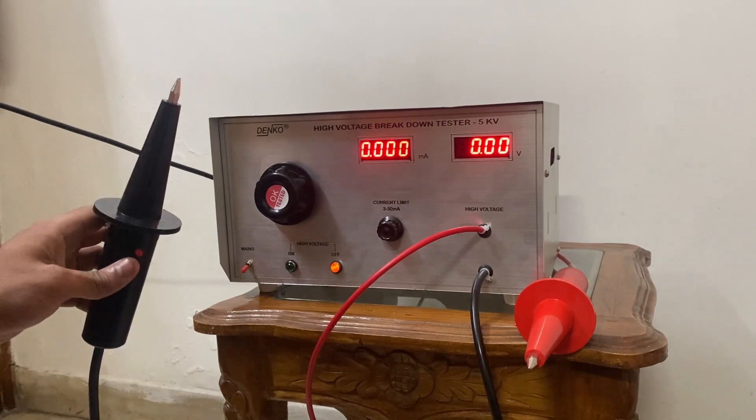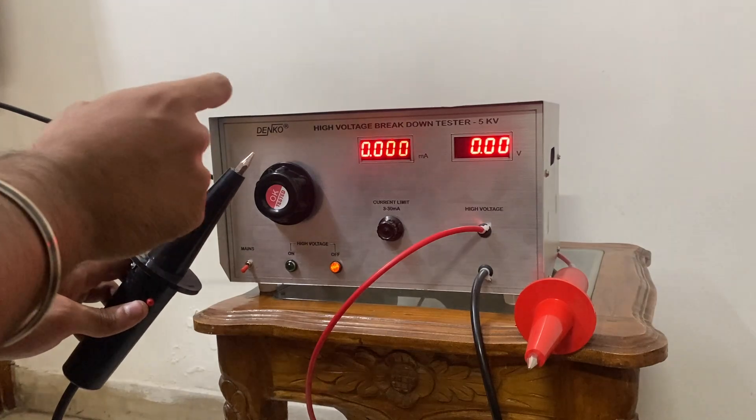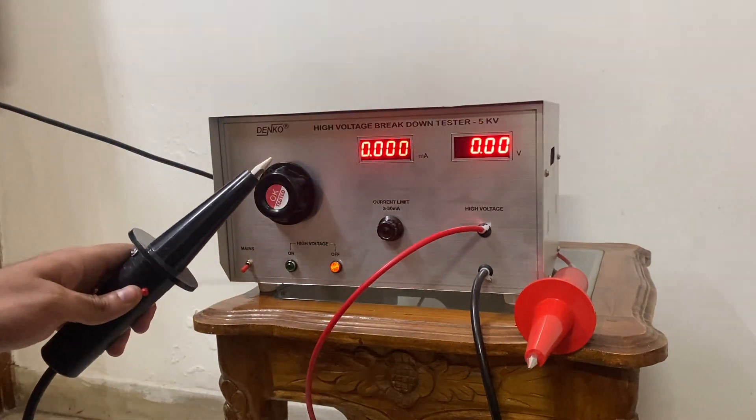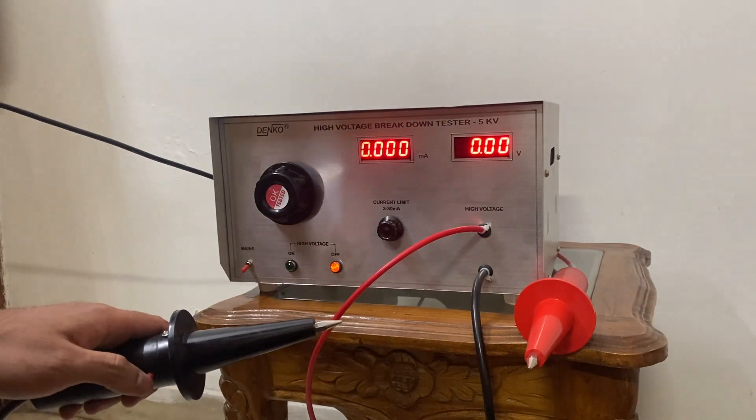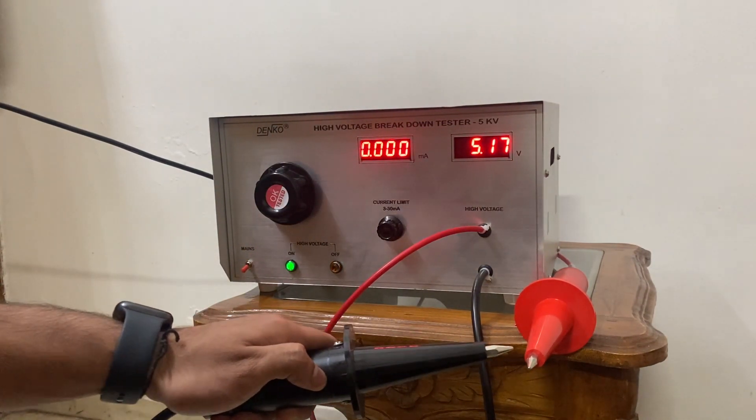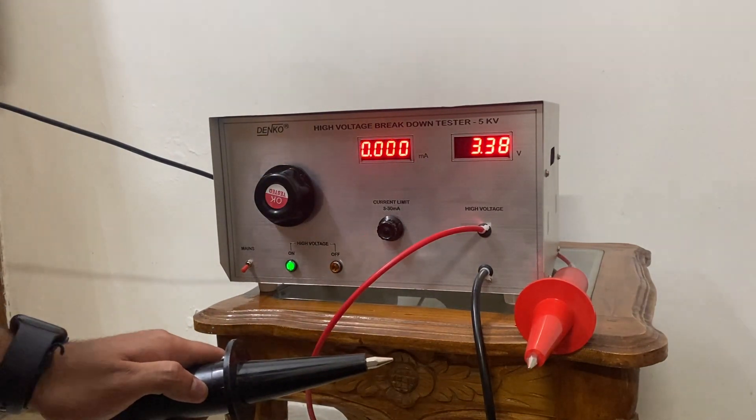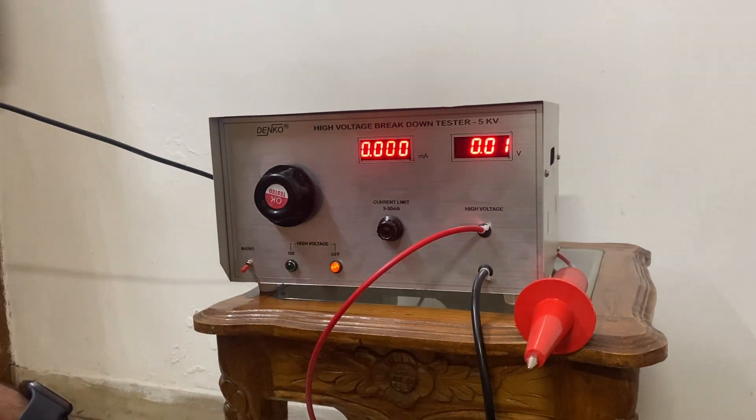The test subject is connected to each end of these probes, and at whatever voltage it breaks down, it's going to show on this meter and trip instantaneously so you can note down the voltage at which it trips. For example, if your product is tripping at 3.38 kV, it's going to show over there.